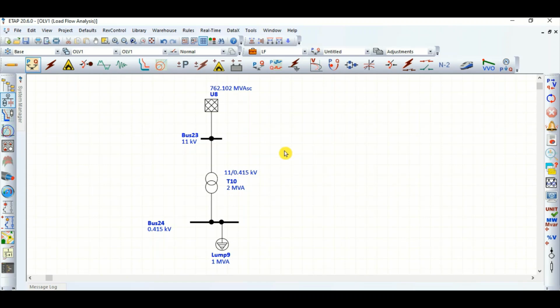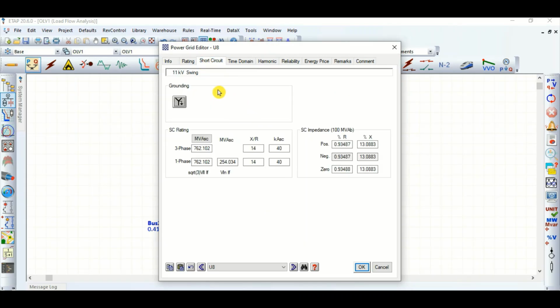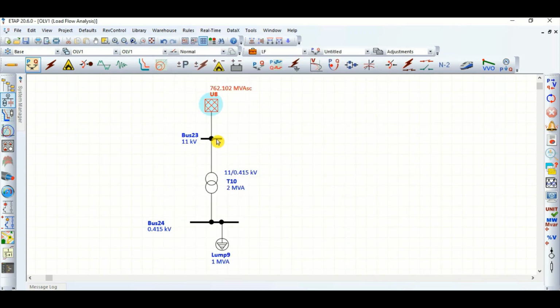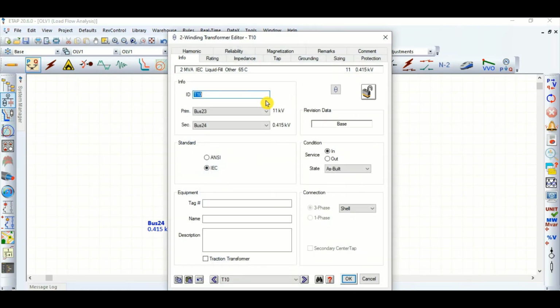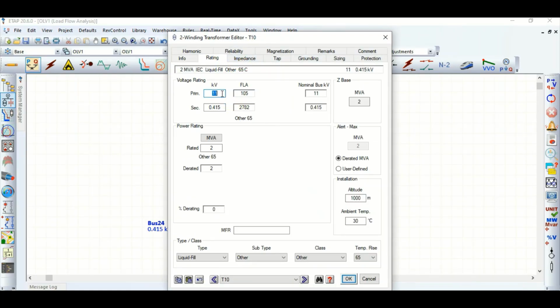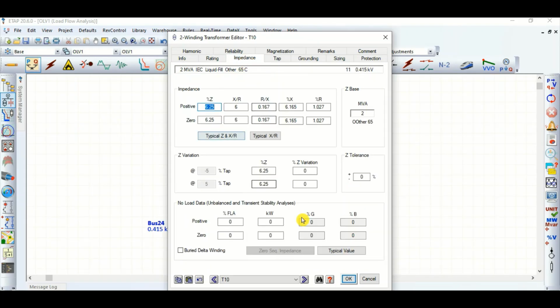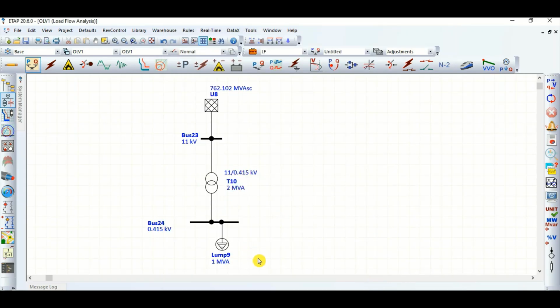In today's video, we will see the impact of transformer no load voltage in load flow and short circuit studies using ETAP. I have modeled one simple network which consists of this grid. This is 11 kV, X by R ratio 14, and short circuit current is 40. This transformer is a 2 MVA transformer, 11 by 0.415 kV. Impedance is a typical impedance I have considered, and the X by R ratio also.